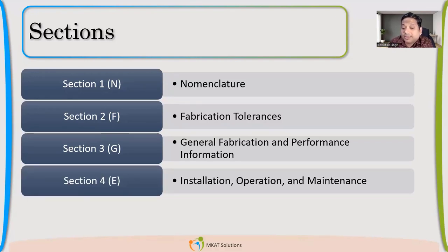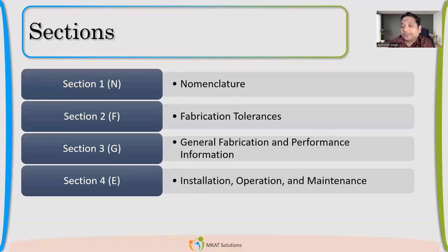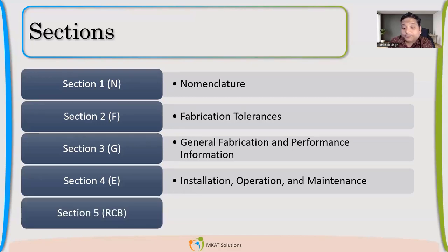Section four talks about installation and operation. You'll also find a chapter on bolt torque tightening sequence. One more very important thing covered in section four is leak testing — specifically what flanges we have to make for leak testing. Other than the flanges which are part of the job, we need to make some additional temporary flanges to do the hydro testing, so we can access and inspect the leakage area.